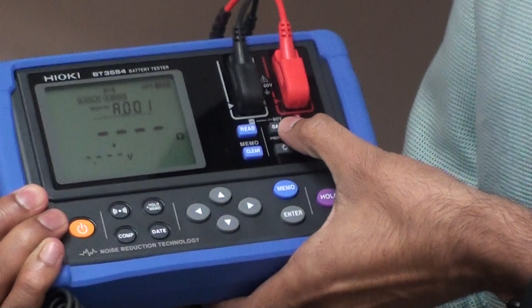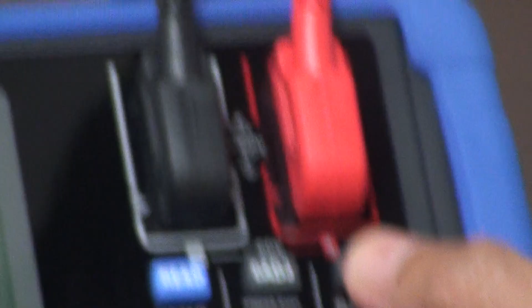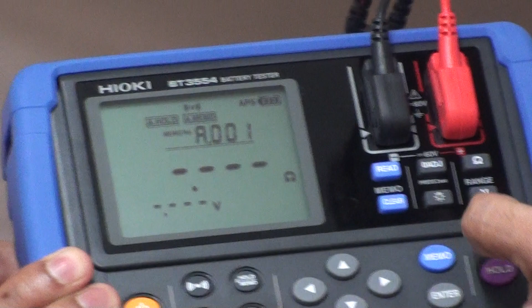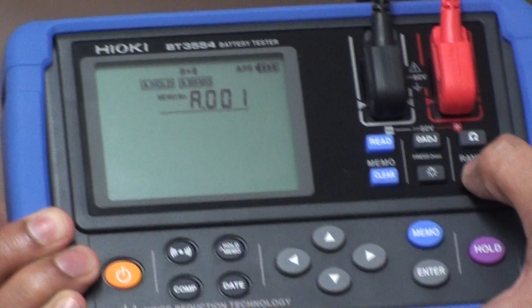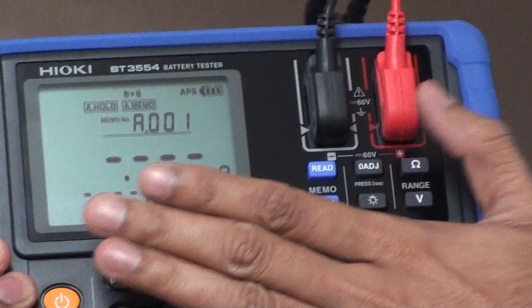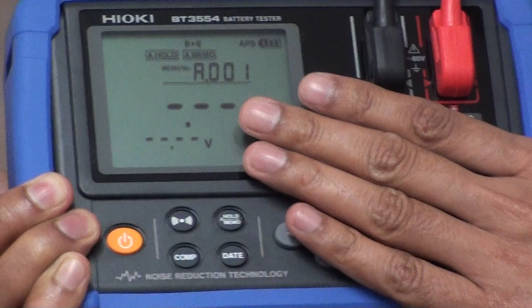So here you can see there is a zero adjustment, there is a resistance setting. You can set 3 milliohm, 30 milliohm, 300 milliohm. Now we move to the 3 ohm. At the same time there is a voltage range. You can set voltage 6 volt to 60 volts. There is a 2 volt in the voltage range. So once you set the 60 volt and resistance around 3 ohm, now your instrument is ready for testing. Once you do the setting for the instrument, you can move to the testing.